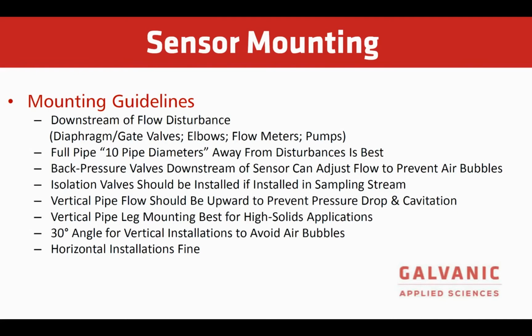So here we can see some of our sensor mounting guidelines. Obviously, we do not want to be downstream of any flow disturbance. For example, pumps, flow meters, or air bubbles that are being formed from these will also be seen. We want to be a minimum of 10 pipe diameters away from these types of disturbance. A little bit of back pressure can cut down on air bubbles present, which will allow the sensor to only see either the oil droplets or turbidity in the sample and not air bubbles.